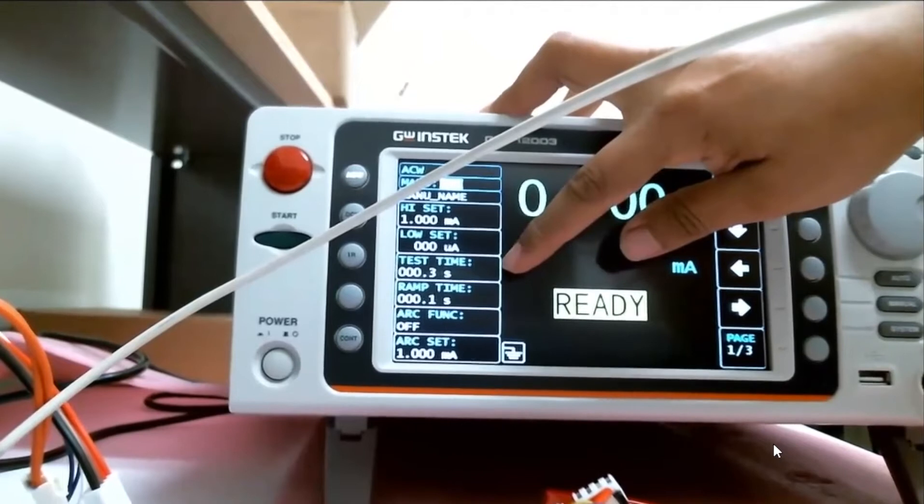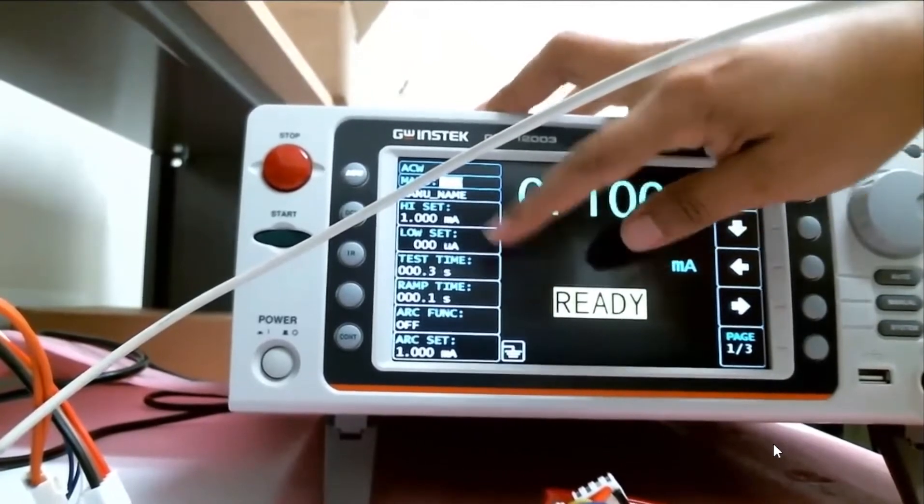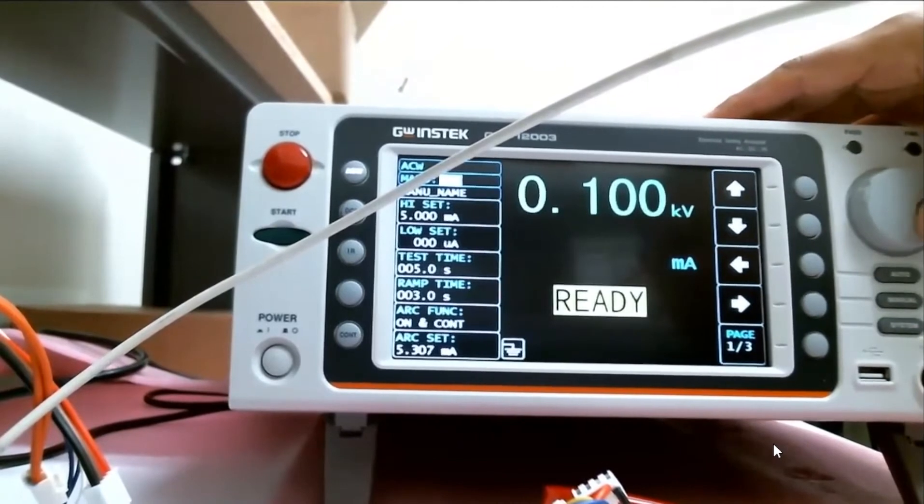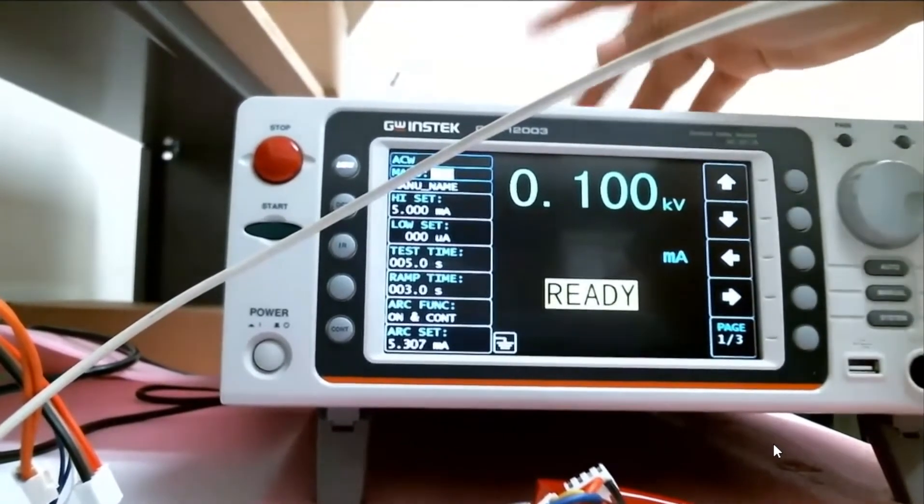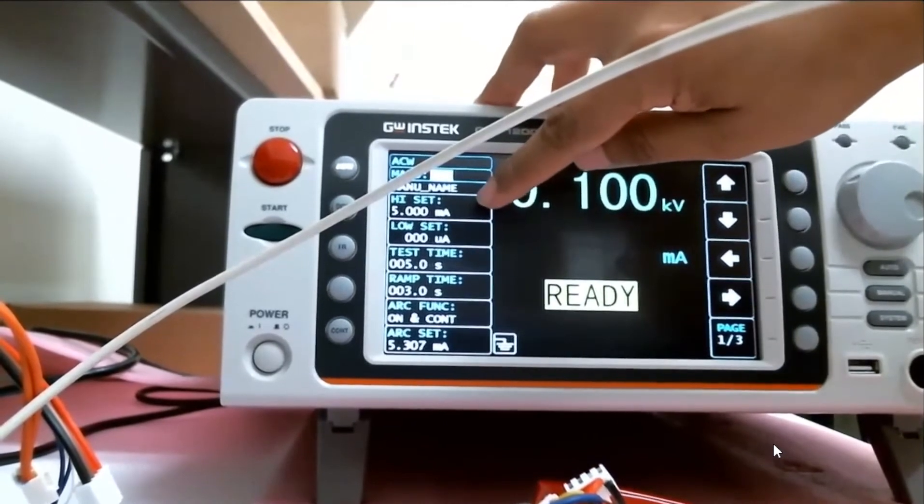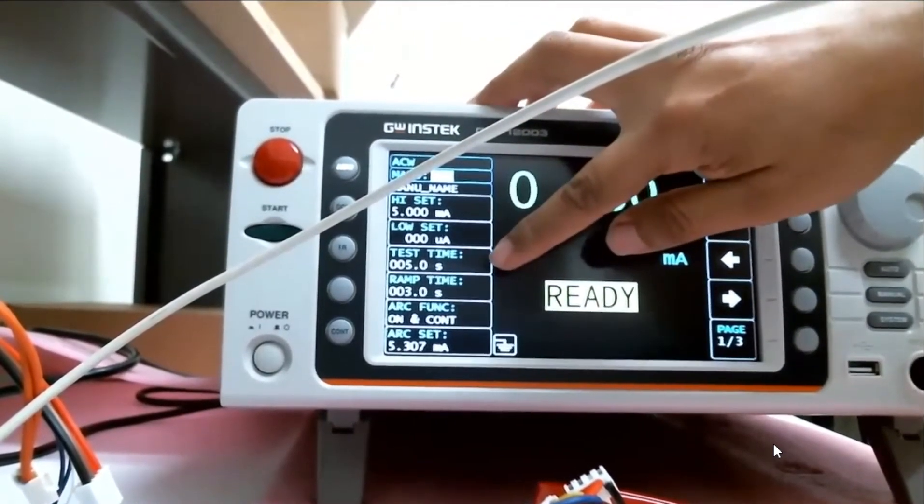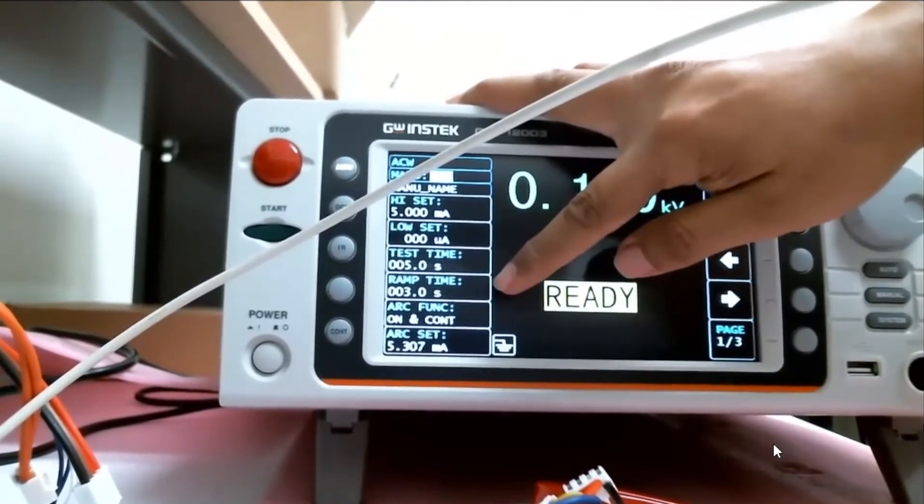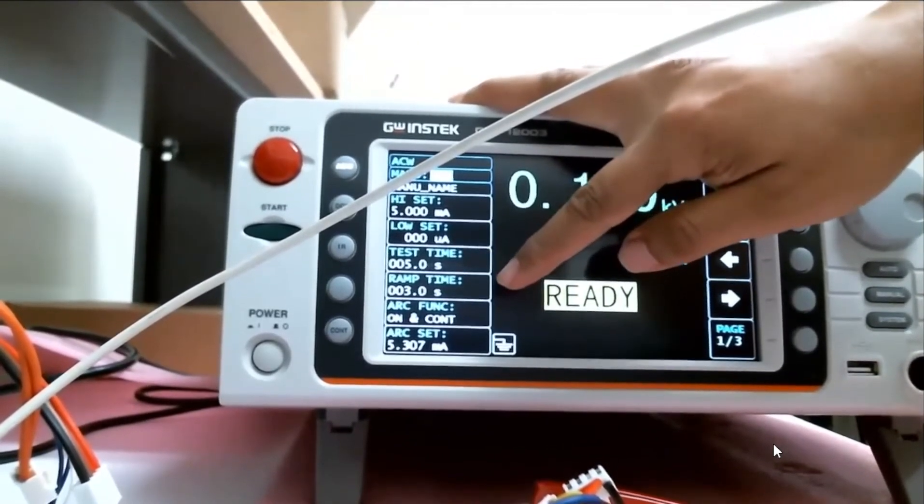Test time, I'm going to run it for about 300 milliseconds, my ramp up time, I'll run—I'm sorry, that's wrong, there we go. In this case, this is actually my example: 5 milliamps is my high set, I will test it for 5 seconds, I will ramp up, meaning that I won't have instantaneous voltage output, it will take some time, in this case 3 seconds.